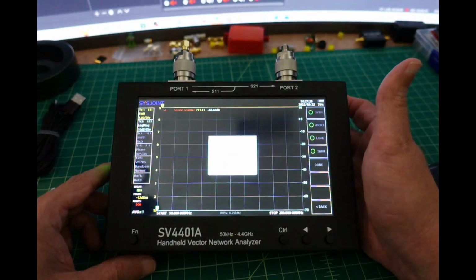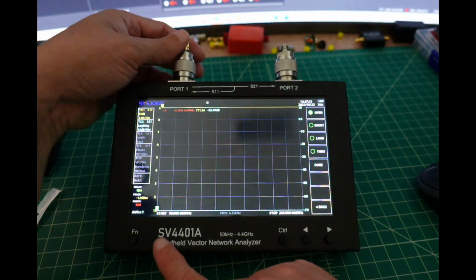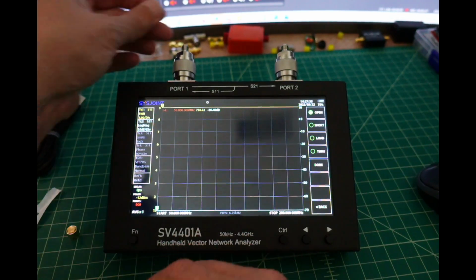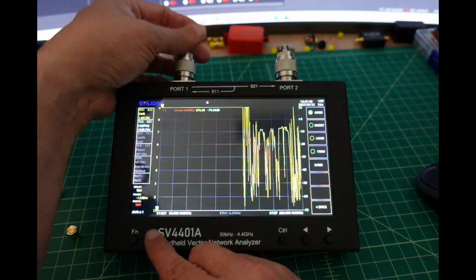And it is. So now I'm going to click open, and it is performing the calibration. Now this screen here was washed out and you couldn't see that. So I'll take a snapshot and roll that in. So the open is done. So what I'm going to do is I'm just going to go ahead and remove our calibration standard. And the next one I'm going to put in here is going to be the short standard.